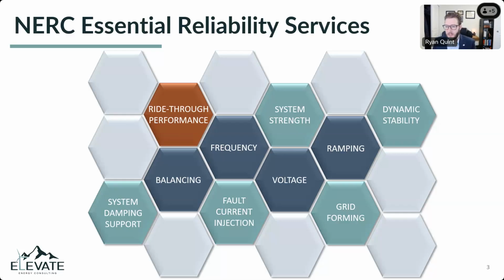We have things like system damping, making sure a predominantly inverter-based system is stable and well damped, making sure we get sufficient fault current injection so our protective relays continue to work properly. Being able to handle and manage the decline of system strength, a term used to define how rigid and stiff that grid is, which has predominantly been provided by synchronous generation. This leads into the use of grid forming technology for inverters, and then managing the increasing focus on dynamic stability, oscillations, controller interactions, and all that stuff we run into with a heavy fleet of inverter-based resources.